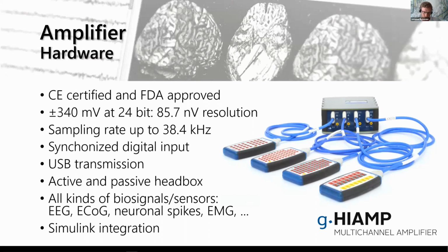The data is transmitted via USB to the PC. We have several headboxes, most importantly distinguished between active and passive headboxes, where stimulation in our context, of course, can only be done via passive headboxes. We can record any kind of biosignals and sensors. And also the Hiamp has a Simulink integration for real-time data acquisition.